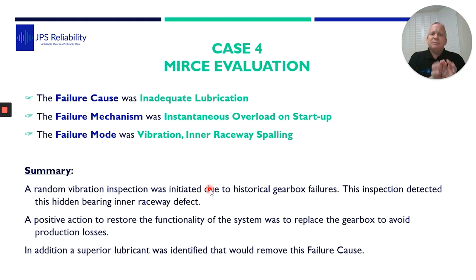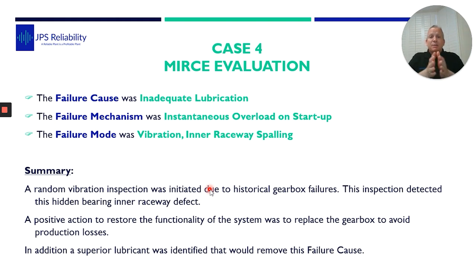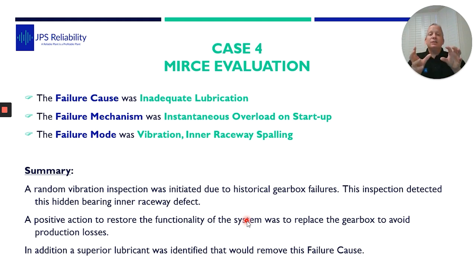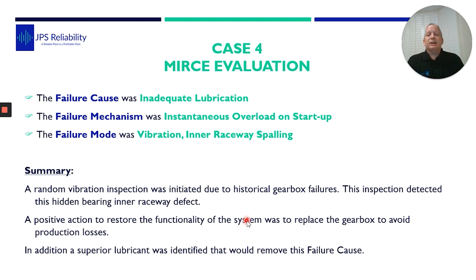The inspection was effectively random in the sense that we were doing a trial to prove they could achieve a higher PF curve and plan and schedule maintenance. We found a hidden defect — one that they would only normally find once the inner race had spalled so much that significant heat was generated in the gearbox, picked up only on the operator's temperature checks.